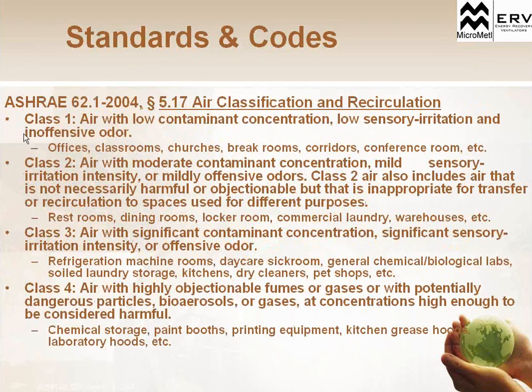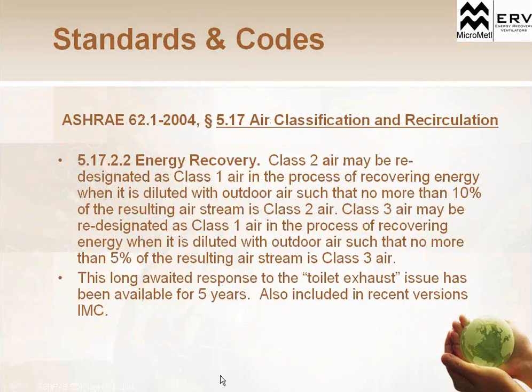As we look at those classifications, you have Class 1 through Class 4. Basically, Class 1 is just return air that can be recirculated back to the system. It's inoffensive with no odor, basically, is what it means. Class 2 is moderately contaminated air, mildly offensive odors. Class 3 and Class 4 are kind of paint booth type equipment, air that has to be exhausted directly from the building. So this code of 62.1 is going to tell you when you can bring that return air and actually use an energy recovery ventilator. If you have highly objectionable air, like Class 4 air, you may not be able to use an energy recovery system on that exhaust air. So that standard would help classify when you can bring that recirculation air back through.